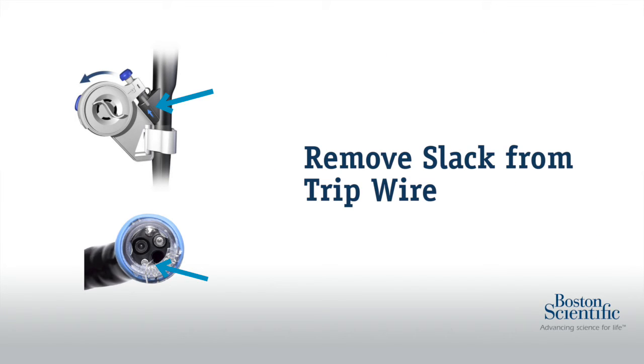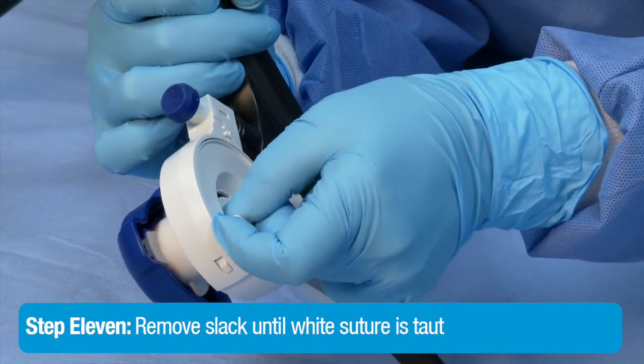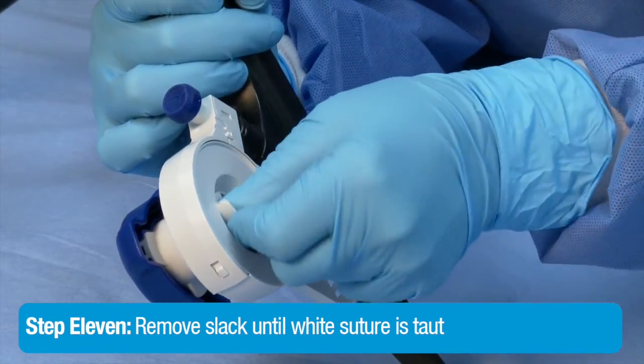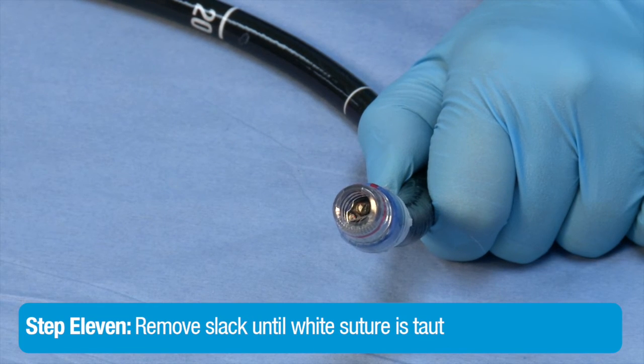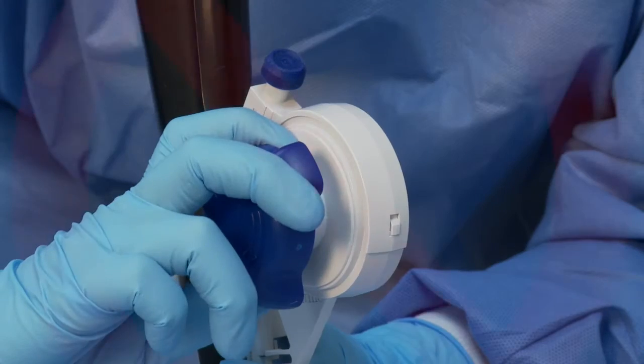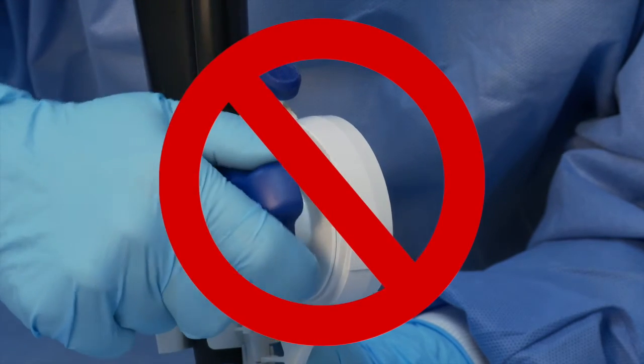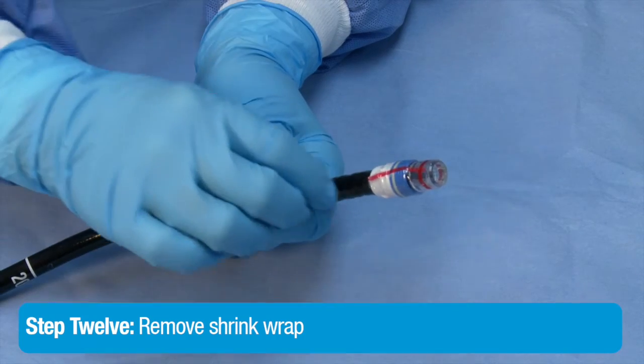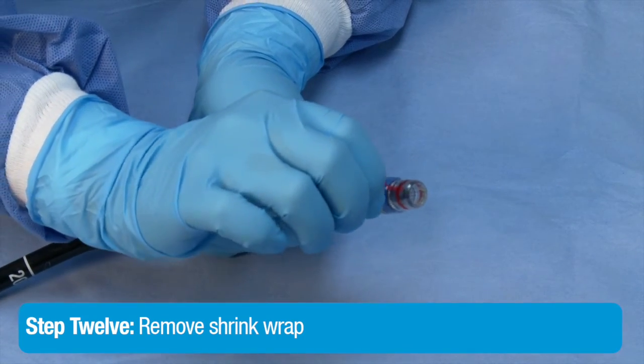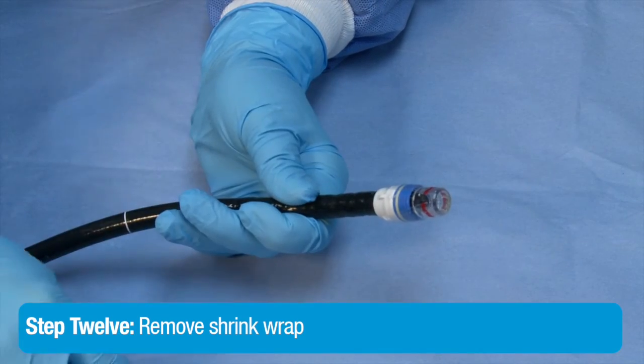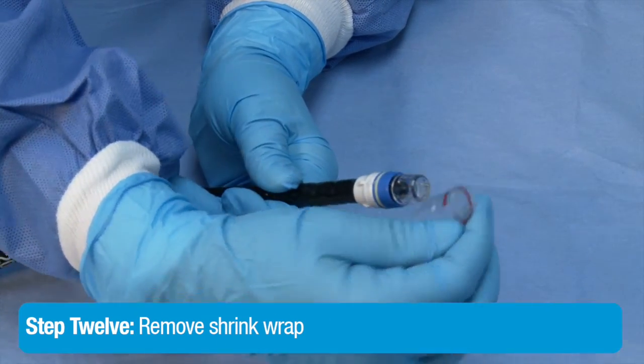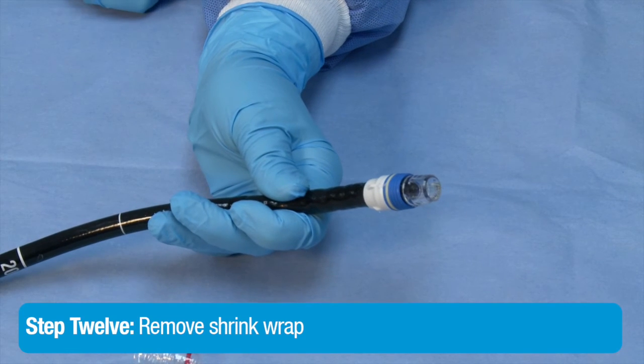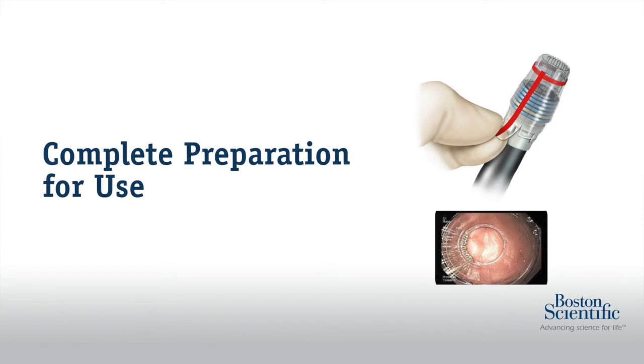Next, remove the slack from the tripwire. To do so, turn the S-shaped knob to take up the remaining slack until the white suture is visibly taut. Do not use the blue handle to tighten. Lastly, carefully remove the shrink wrap from the ligator cap by pulling the marked tab from the soft end of the cap without disturbing the ligator bands and threads. You have now completed your preparation for use.